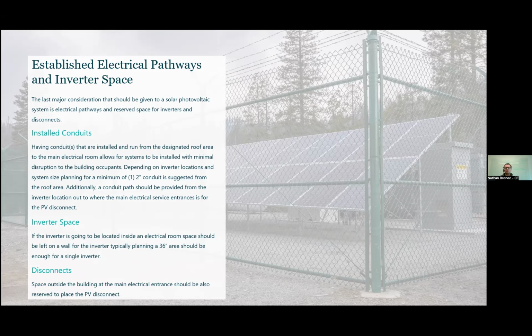And so when we do a solar ready building, we're really wanting to make sure we have established pathways up to the roof area that we have slated as that solar expansion point, all the way down to the main electrical room. Now, the number of conduits that you need and the size of them is going to vary. A lot of times when we're talking rooftop solar, we usually are locating inverters up on the roof. So we're running an AC feed through the building out to a disconnect right at the service entrance, and then back out of that disconnect into the main switchboard of that building.